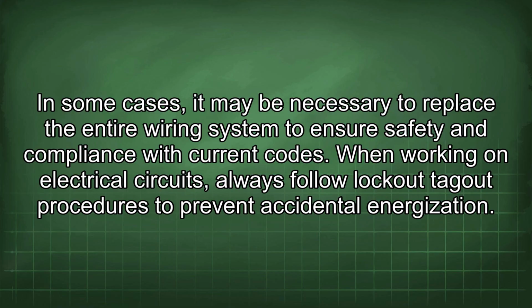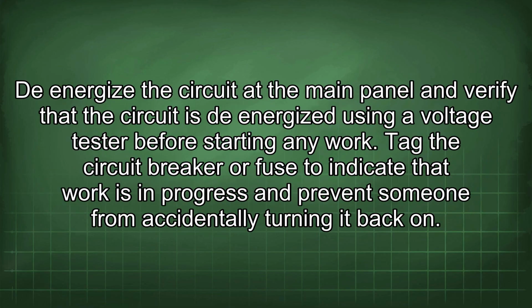codes. When working on electrical circuits, always follow lockout-tagout procedures to prevent accidental energization. De-energize the circuit at the main panel and verify that the circuit is de-energized using a voltage tester before starting any work. Tag the circuit breaker or fuse to indicate that work is in progress and prevent someone from accidentally turning it back on.